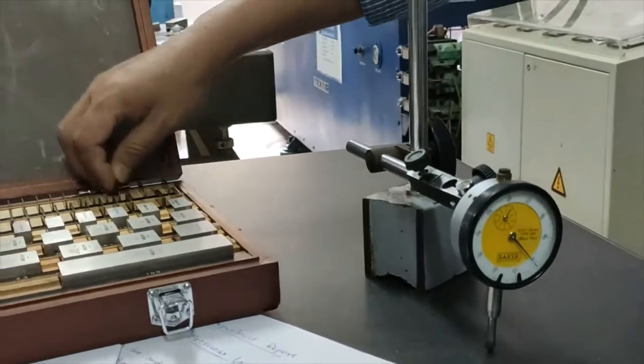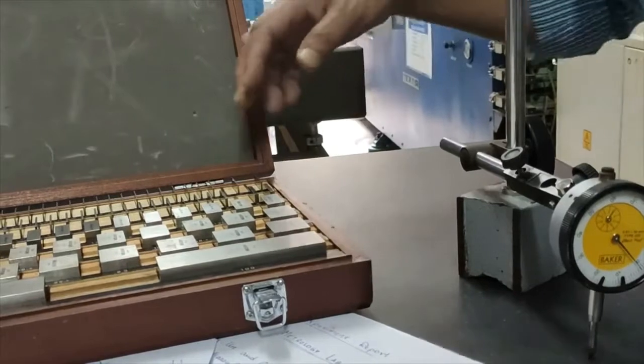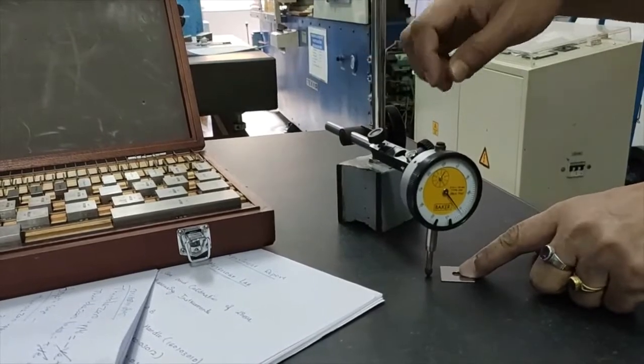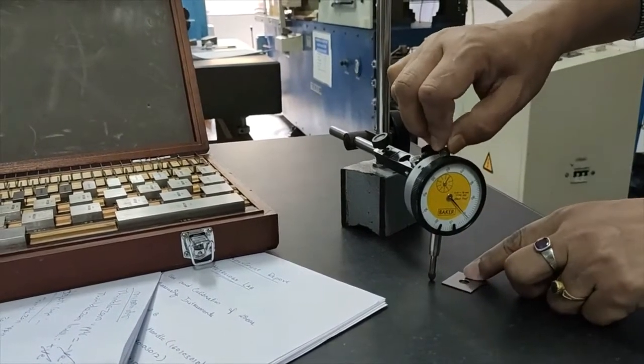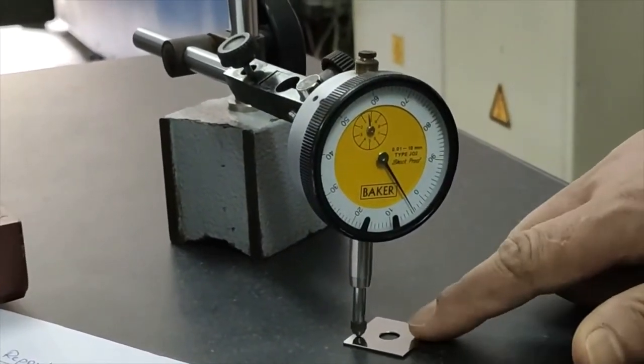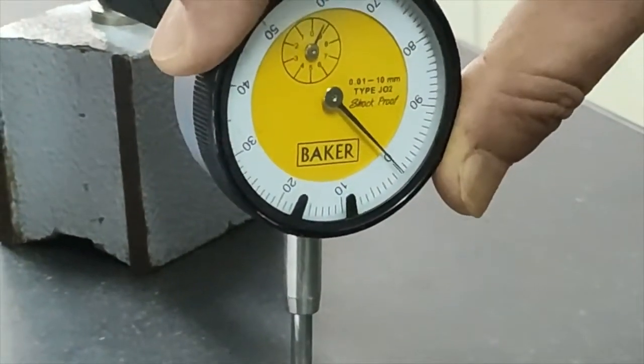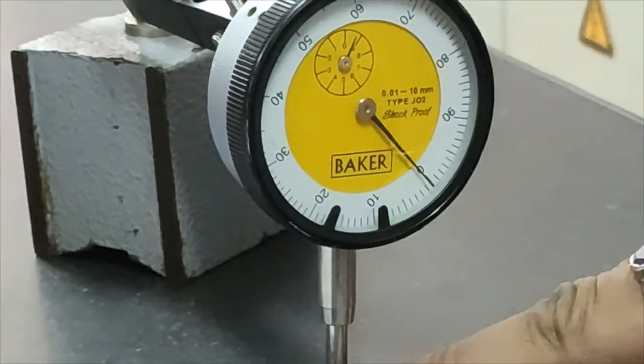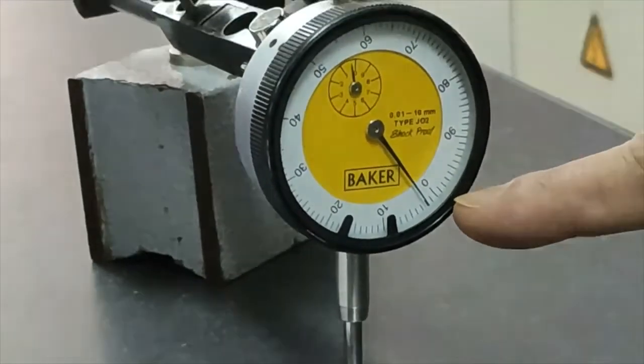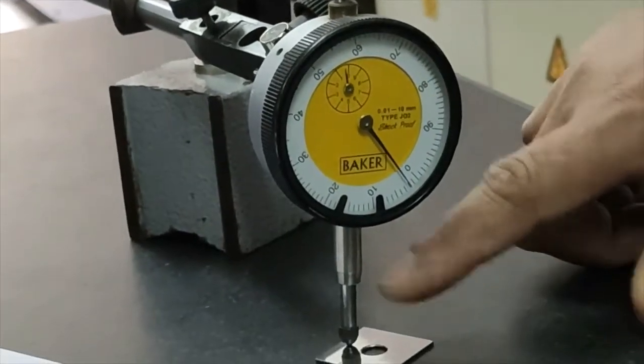Now I will put 1 mm by lifting it. Now see the reading. It is coming error, 0.02 error. So like this way up to 10 mm I will calibrate it.